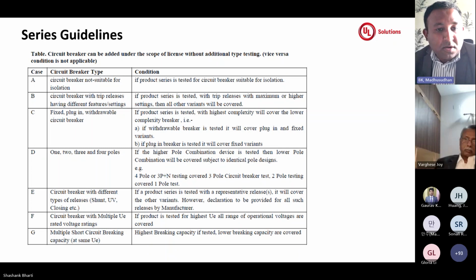Then in a similar way for plug-in type and withdrawable type. So if we are covering a complexity variant in the base construction, these additional constructions can be added without any testing, with the documentation. And in a similar way for 1-pole, 2-pole and 3-pole variants. Suppose today the coverage was only for a 4-pole or a 3-pole plus neutral variant, and tomorrow, for the same construction without any changes, manufacturers want to add a 2-pole or a 3-pole variant. With the documentation review, the licenses can be updated.